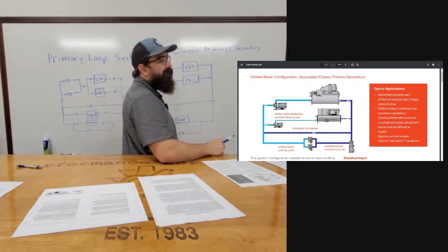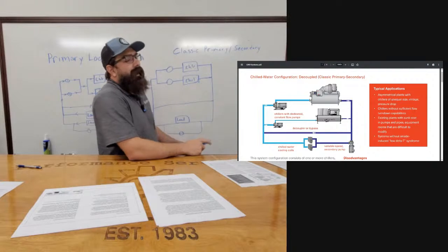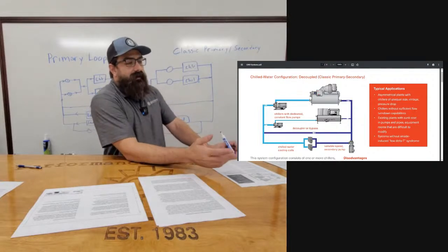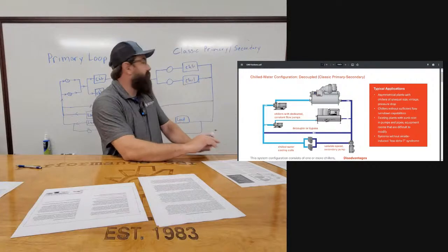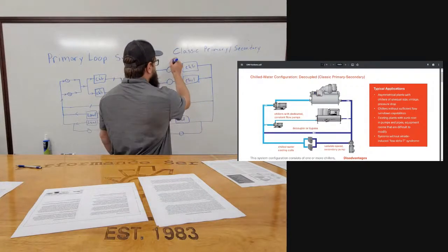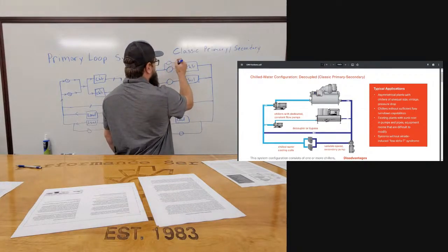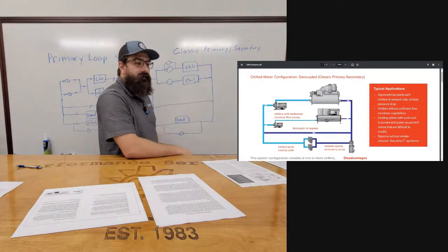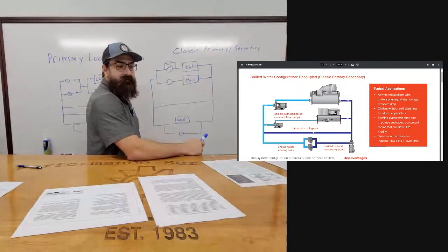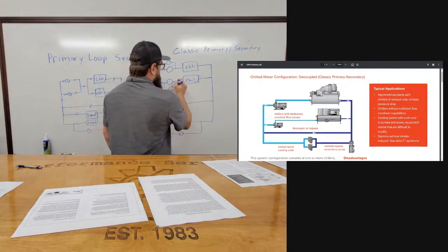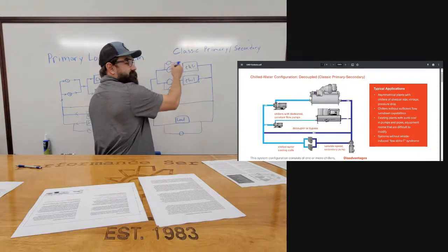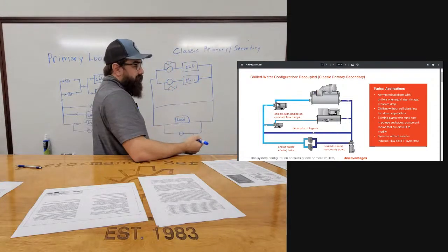No. I get what you're talking about. Yes, it could. I've seen some. I know what you're referring to. Like, a lot of times what you would have is two pumps like that feeding one chiller. That's more common than having a bypass. So this system would have four pumps, and then I could lead lag each of these pumps based on that chiller. So it just depends.